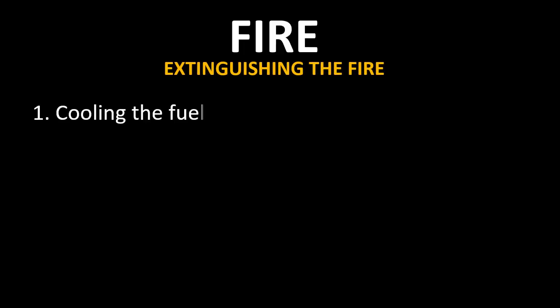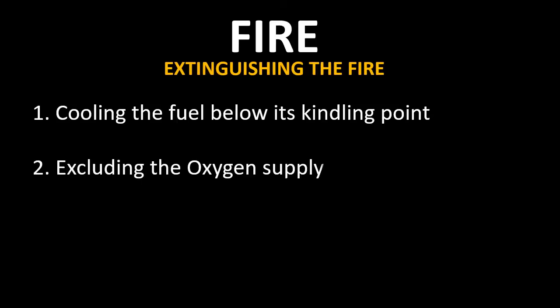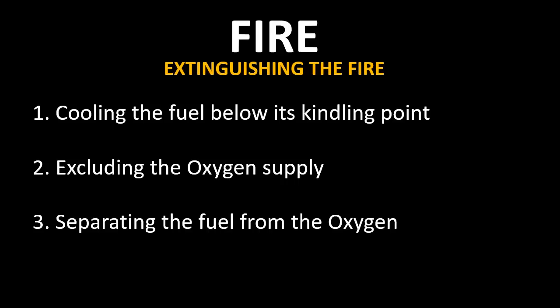Depending on the nature of the class of fire, the best method for suppression may be one of the following: number one, cooling the fuel below its kindling point; number two, excluding the oxygen supply; and number three, separating the fuel from the oxygen. These methods have led to the development of different types of extinguishers for different types of fires.